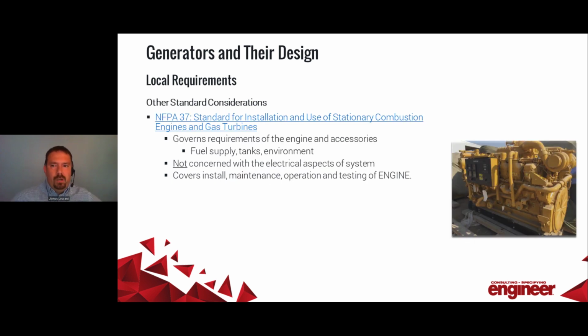So beyond the local code requirements, you'll also have standards that apply, right? So NFPA 37, which is the standard for installation and the use of stationary combustion engines and gas turbines. The scope of NFPA 37 is really written around the prime mover portion of the generator. It's the engine itself, right? It covers things like install, maintenance, operation, and testing of that engine. It doesn't care about the electrical aspects of your system. It doesn't care about the alternator. It doesn't care about the transfer switches downstream or the associated distribution. It's really related to the fuel supply, the tanks, the environment.